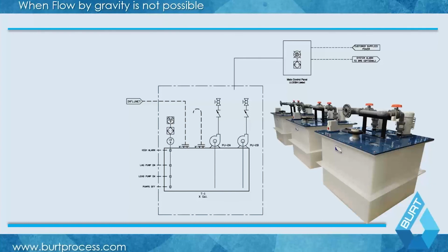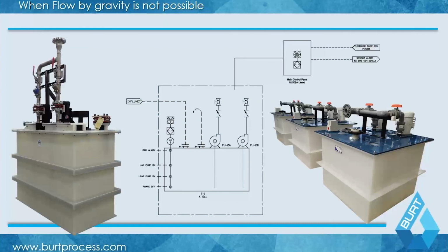And this comes up very often when you have a pH neutralization system that's going to be located, say, on grade, or your piping has to be sloped underground. And you don't necessarily want to locate your pH system in the ground or in a pit because of the various complexities that are involved in it. People do need to look at utilizing a lift station.